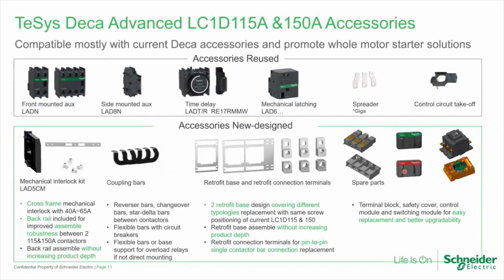So let us talk about accessories associated with this contactor. Many accessories, you will find, are reused from the existing TeSys Deca range. Be it front mounting contact or side mounting contacts. So auxiliary contacts, which are LADN and LAD8N, they are from the existing Deca series. So they are not something new. You can very well use existing contacts with this contactor. All the timer relays and mechanical latch block also can be used from the existing range. The busbar connections are the ones which are applicable for the Giga series. And if you want to take control circuit from your power terminal, the connections which were available along with TeSys Deca can be used.